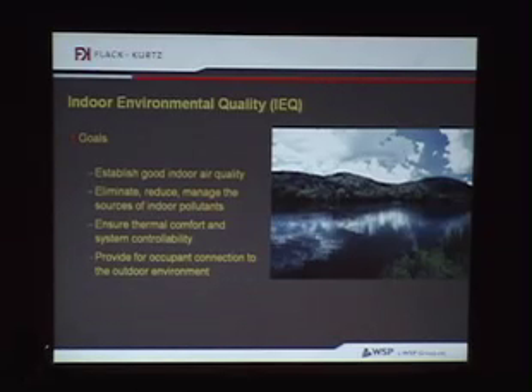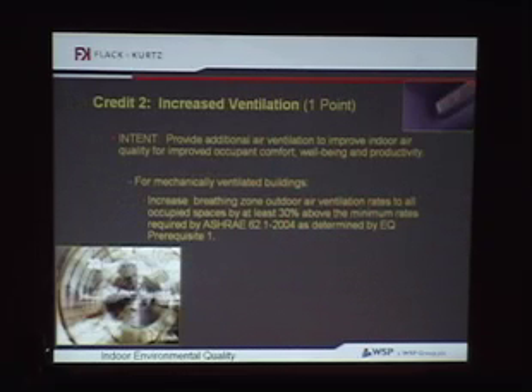Indoor environment quality was always foremost in mind, and in addition to energy efficiency savings, the underfloor air system helps improve the indoor environment of the space - both in terms of the cleanliness of the air in the occupied breathing zone, and individual controllability of the air conditioning at each workstation. ASHRAE, one of the governing engineering societies, now recognizes that because clean, fresh air is delivered right to the occupant, you can actually provide less fresh air than otherwise required by an overhead system, further increasing energy efficiency while still providing the indoor environmental benefit of a standard amount of outside air.